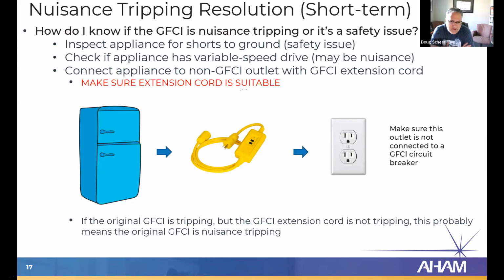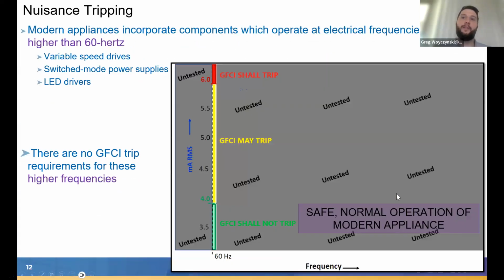So variable speed evaporator fan motors, are you suggesting they can be causing a nuisance trip? Totally, yes. So variable speed fans, pumps, compressors, they're operating safely, but they're operating at high frequencies, which today there's no GFCI requirements for. So your fan motor is probably safe. But if you do have a variable speed fan, compressor, or pump, that makes it more likely to be nuisance tripping, because those components are generating high frequency electricity that the GFCI is not required to account for today.